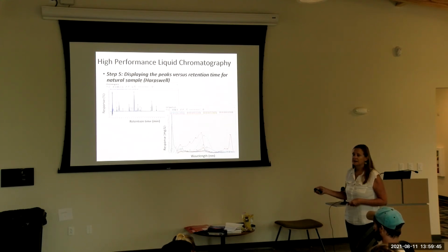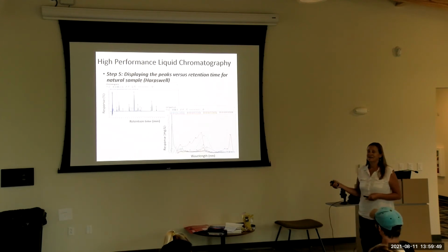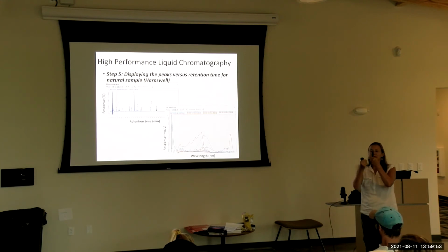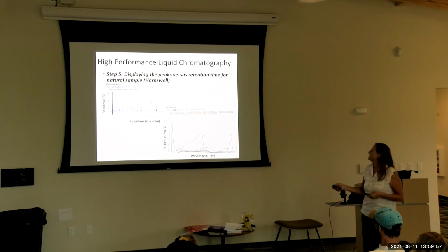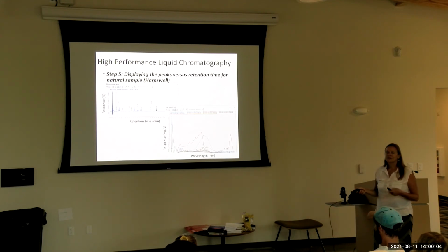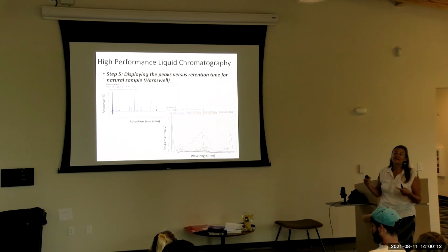wavelengths. This particular instrument detects at 2 different wavelengths. As the material is going by the detector, there's actually 2 light sources, and so you can measure the peak response at, say, 440 and the peak response at 660. Some of your pigments might have a signal in the blue, but not in the red, and so those two peaks may separate based upon the wavelengths that you choose.